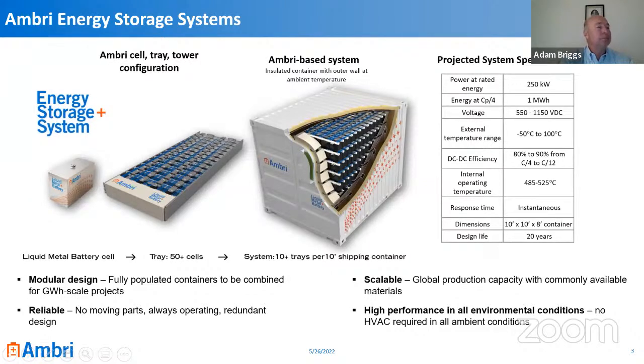Now the other question, about low usage. The battery system is designed to maintain its operating temperature, with no assistance from electrical power for heating, down to about 0.5 cycles per day. So this battery is designed for applications where you'll reasonably predictably do a full charge and discharge every day, typical of a solar plus storage or renewable integration project. Of course it's possible usage could stop altogether, and if so you have choices. One would be to just let it cool down, which would take 10 to 14 days to reach room temperature.